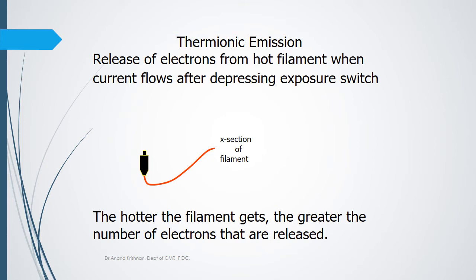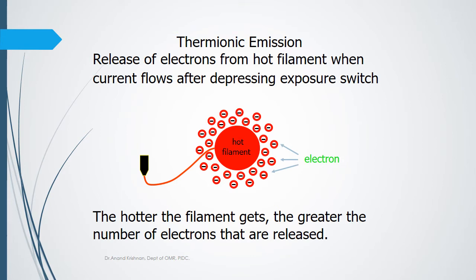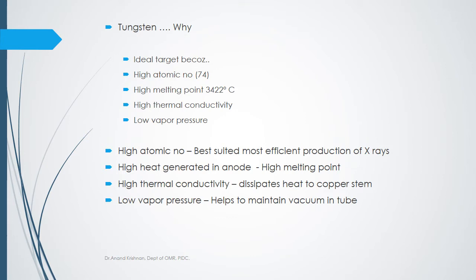X-ray production is based on the principle of thermionic emission. When electric current is passed through the tungsten filament at the cathode, it heats up and emits electrons. These electrons travel and strike the target anode. Tungsten is used in both cathode and anode because it is an ideal target material — it has a very high atomic number, high melting point, high thermal conductivity, and low vapor pressure.